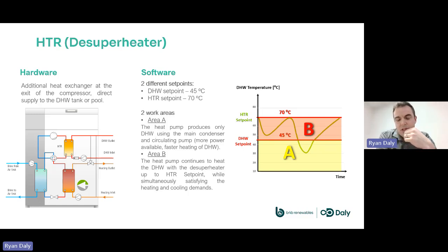In our experience, this really only works in buildings that have a higher heat load. So when the heat pump's having to work harder, it works really well. I have this in my own house, but because we have a low energy house, the HTR doesn't function as well because we're running our underfloor at really low temperatures, so it doesn't kick in as much.